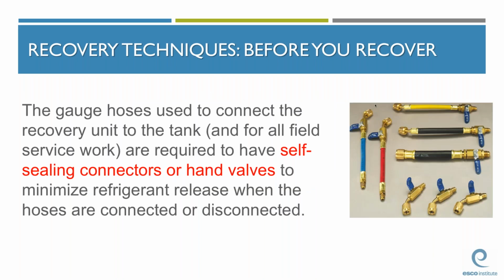It's important that you also stress, both in the classroom and in your labs, that refrigerant hoses are required to have low loss fittings on them. These fittings can be self-sealing or manually manipulated. And it's always a good idea to make sure that your students know how to use them.